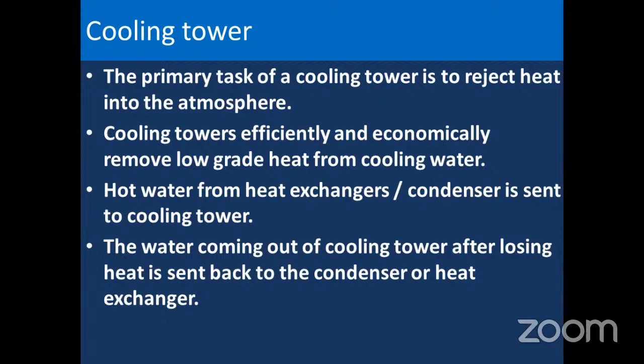Up to this, it's okay, sir. Right, sir. Am I right? Is it okay for you? Actually, we are getting water from sea. Let us see one example. It is sent to the condenser. In the condenser, the steam is converted into water. The seawater gets heated up to nearly 8 or 10 degrees centigrade, and the hot cooling water is sent back to the sea. Now, we are not sending it back to the sea. We are recycling it into a cooling tower, and we are getting it back at the ambient temperature, theoretically, and once again we are circulating it into the condenser. That's all.